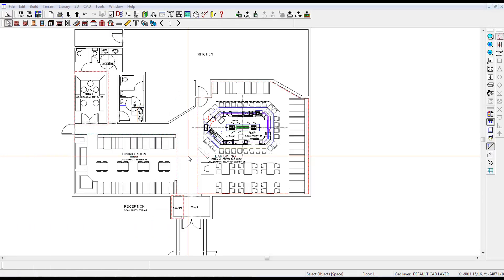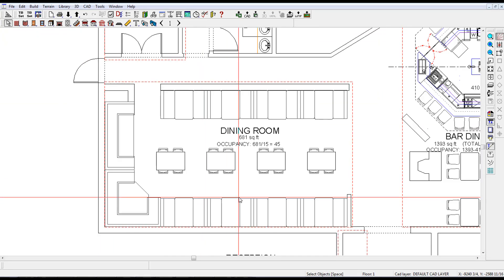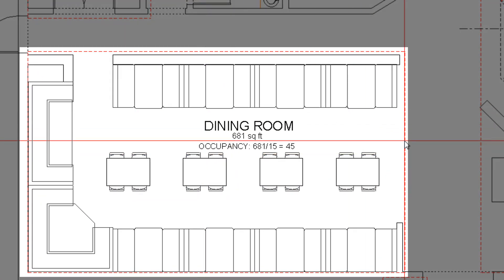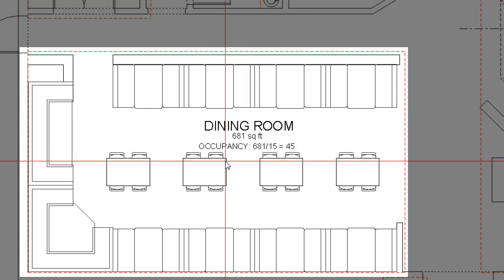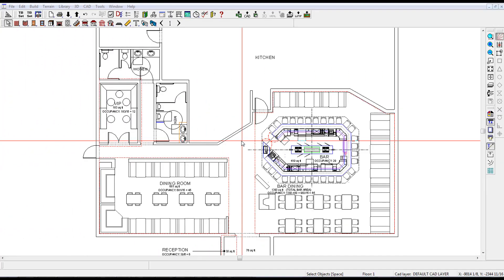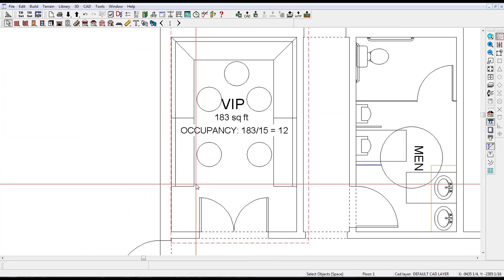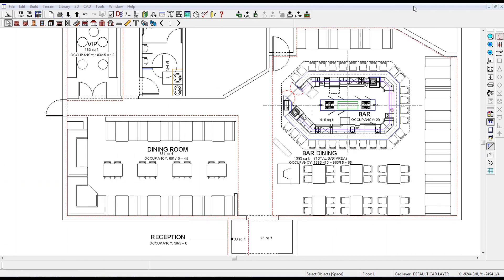The fourth area of this facility is the dining room. In order to calculate occupancy, we can only use the net area as depicted within this border, which is 681 square feet, and because we're using tables and chairs, the occupancy for the dining room is 45. The VIP room, which is 183 square feet and has tables and sofas, we again apply 15 square feet per patron for a total of 12. If the dining room were a dance floor, IBC would allow 5 square feet per patron, which would yield an occupant load of 136 in that area.